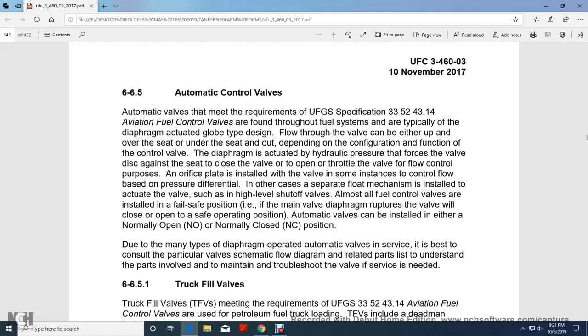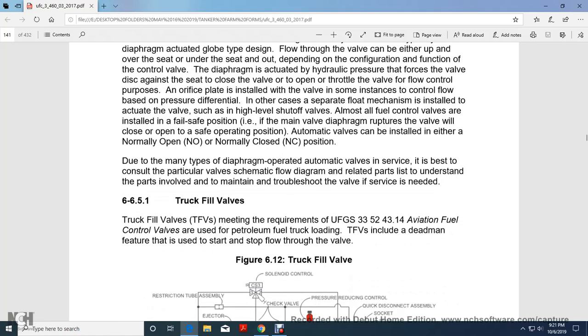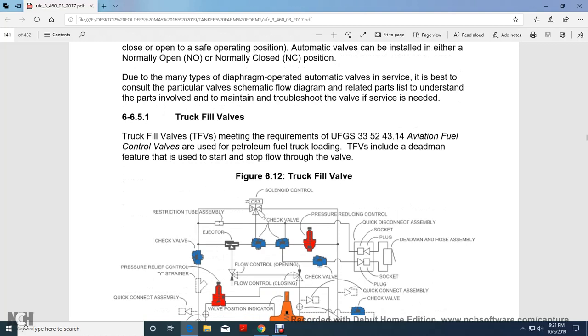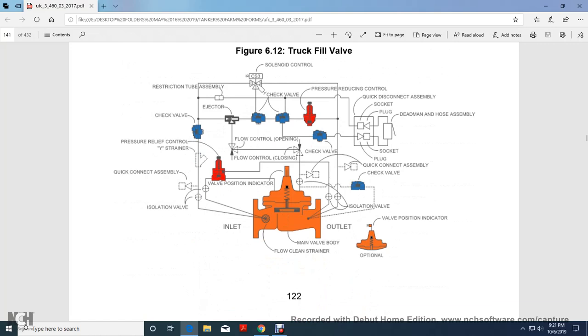Automatic valves can be installed in either a normally open or normally closed position. Due to the many types of diaphragm-operated automatic valves, it is best to consult the particular valve's schematic or flow diagram to understand the parts involved, to maintain and troubleshoot the valve when service is needed. The truck fill valves. Truck fill valves, or TFVs, meet the requirements of UFGS 33 52 43.14. Aviation fuel controls are used for petroleum fuel truck loading. The truck fill valves include the dead man feature to start and stop the flow through the valve.